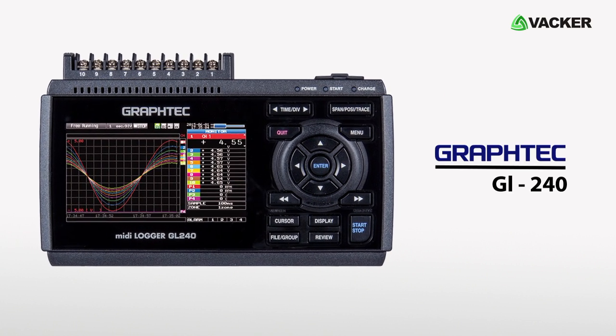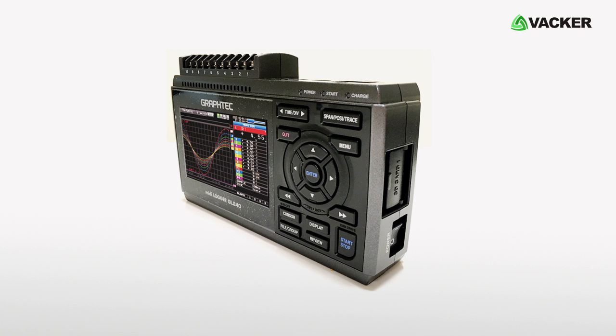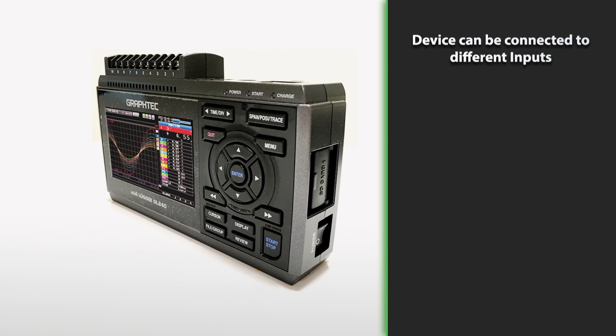This is the Graphtec GL240, a 10-channel data logger with a 4.3-inch color graphic display. The GL240 is a high-accuracy portable USB-connected data logger which can be connected to different inputs, ranging from voltage plus or minus 20 millivolts to plus or minus 100 volts, and thermocouple.